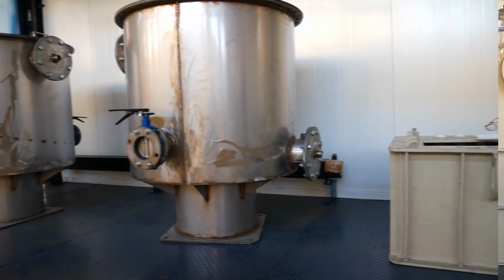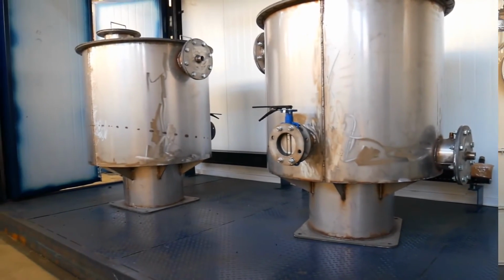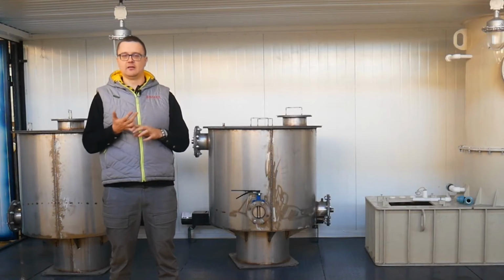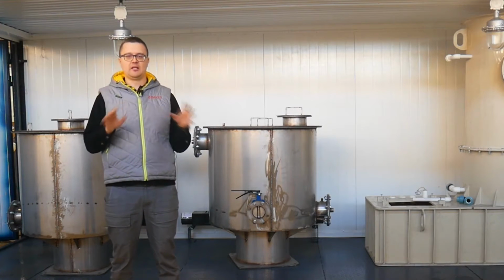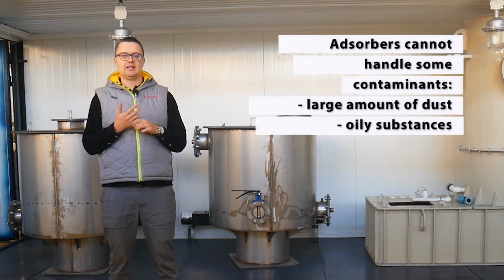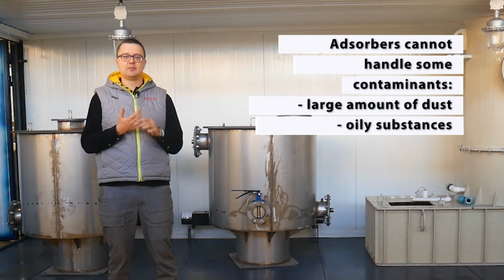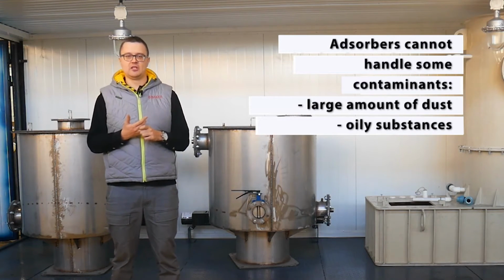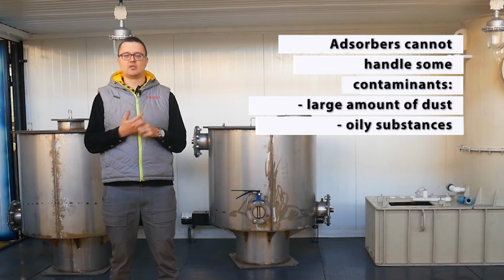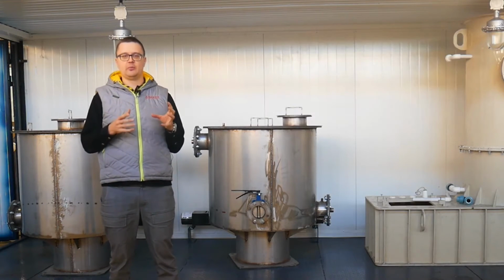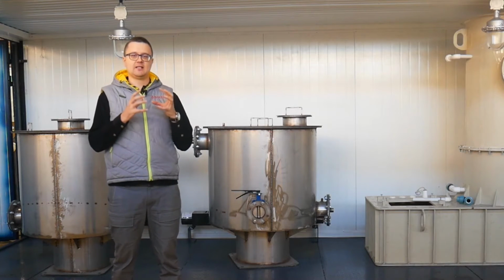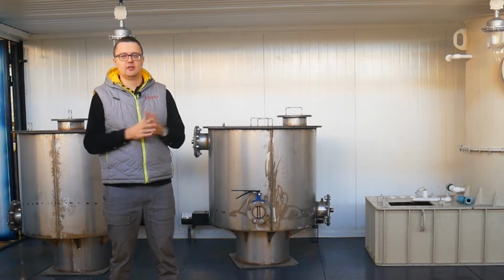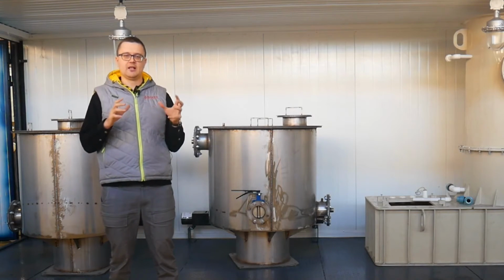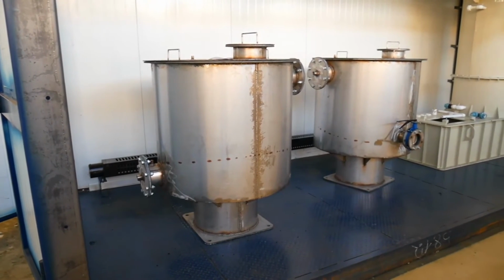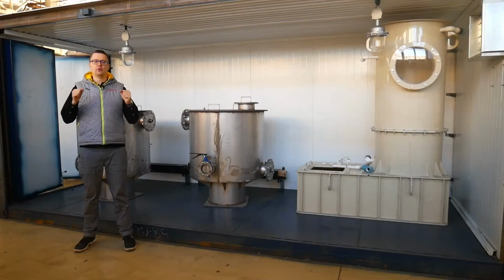What should we pay attention to when selecting adsorbers? Naturally, first and foremost, the most important point to pay attention to is the type of pollutant. Adsorbers don't always work with all manner of polluting agents consecutively. For example, a large amount of dust or oily substances will immediately block all pores in the adsorber, and this will result in the adsorber ceasing to work effectively. And because of this, if there are any forms of pollutants that can cause trouble when operated with adsorbers, they should be removed by a pre-filter, a special form of pre-filter.